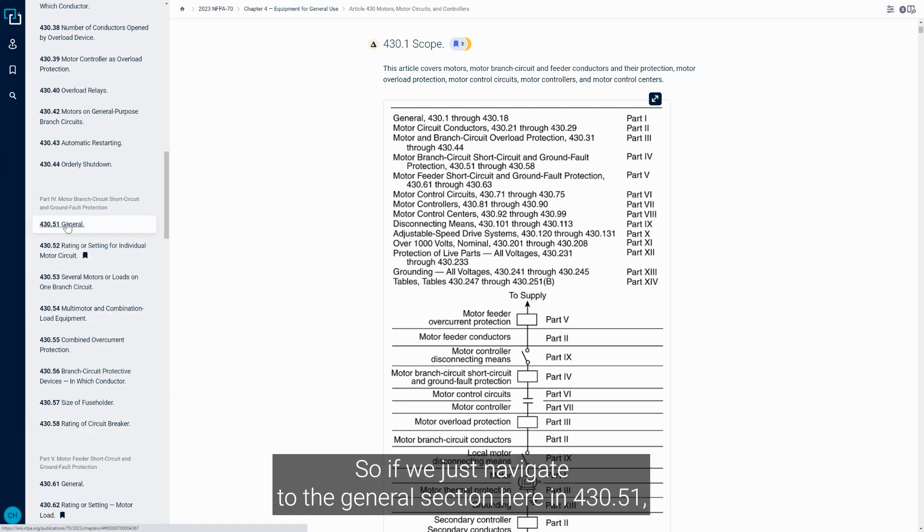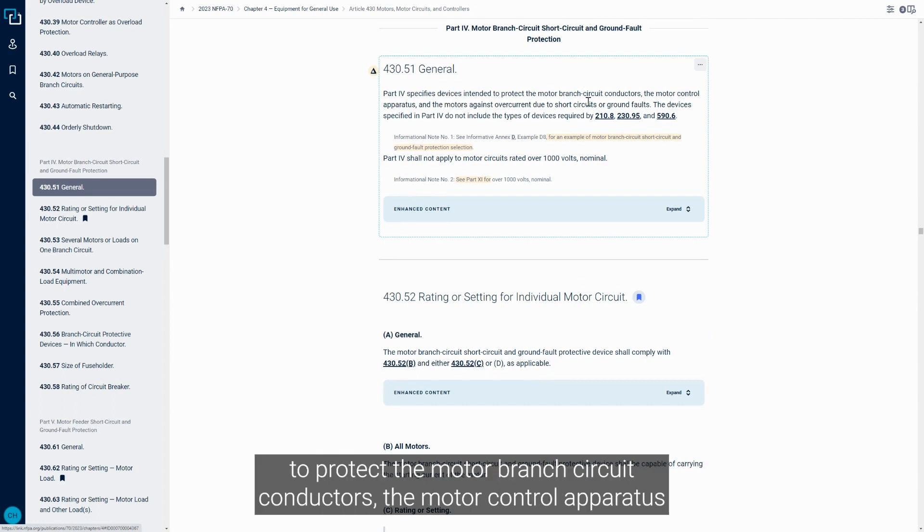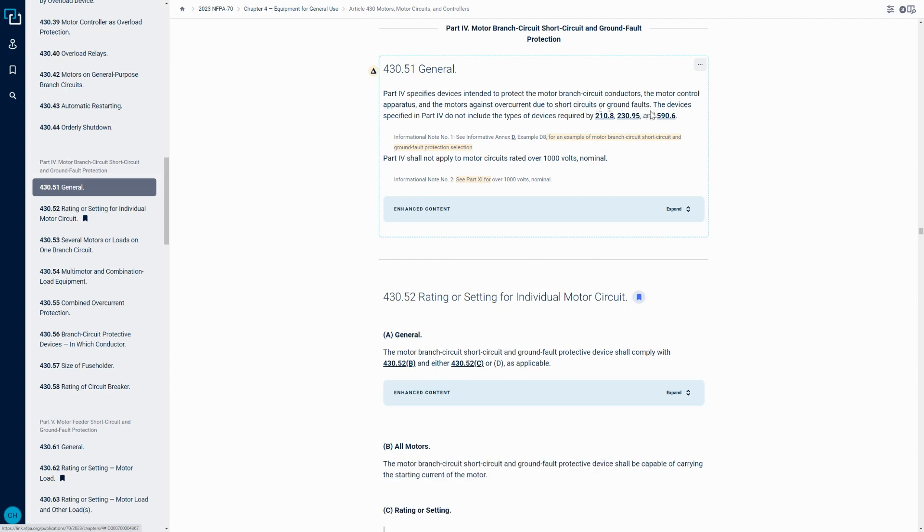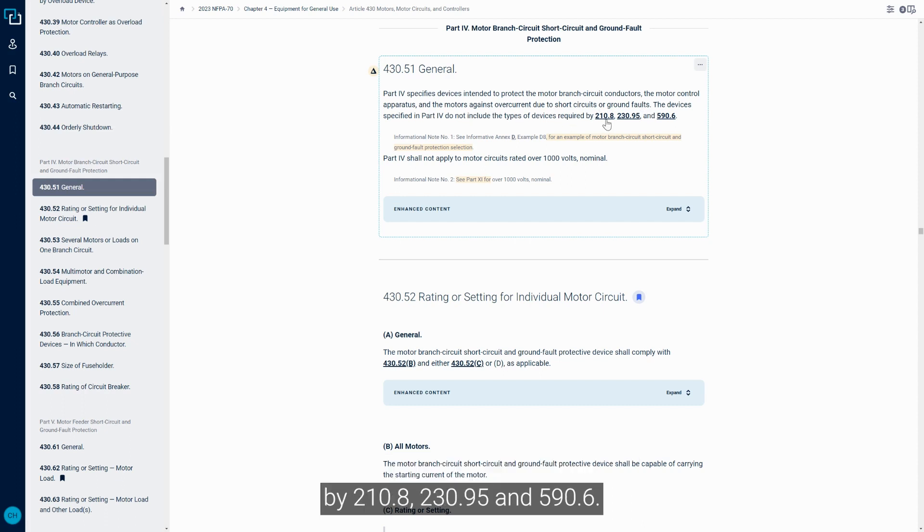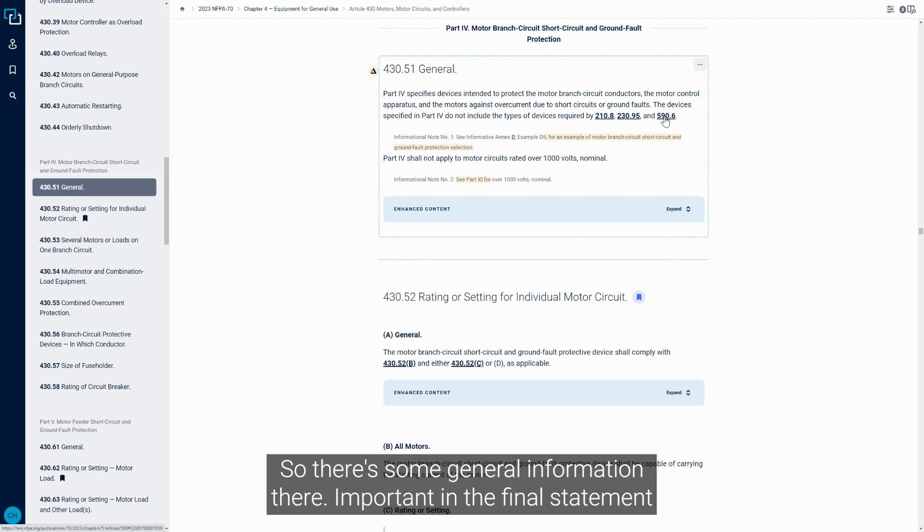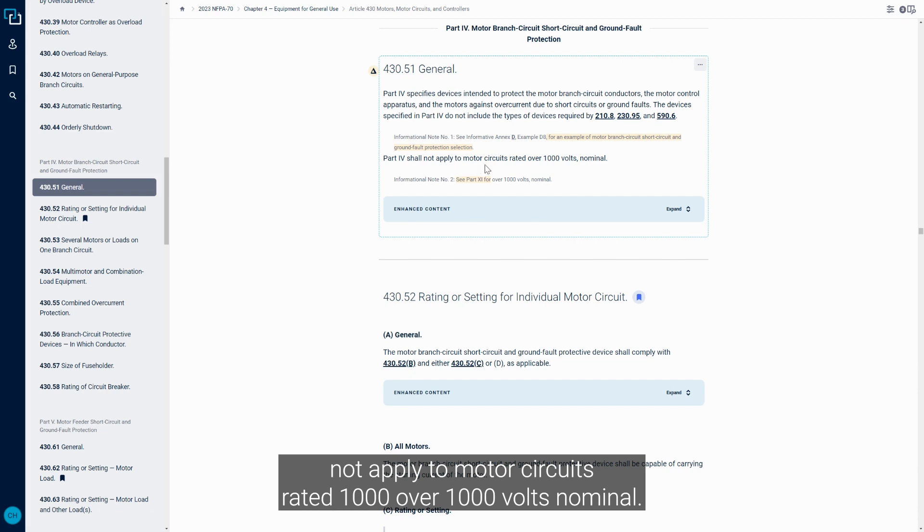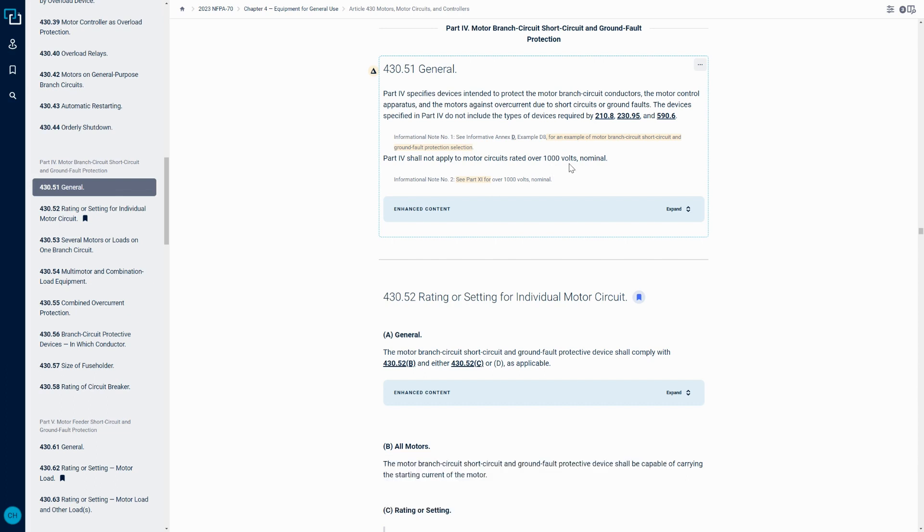If we navigate to the general section in 430.51, we have the initial statement: Part 4 specifies devices intended to protect the motor branch circuit conductors, the motor control apparatus, and the motors against overcurrent due to short circuits and ground faults. Important in the final statement is that Part 4 shall not apply to motor circuits rated over 1,000 volts nominal, so it has to be less than 1,000 volt rated motor.